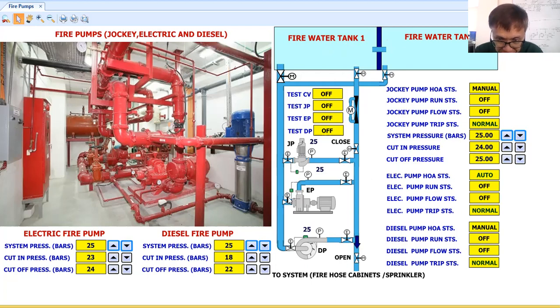So that is how they are checking this electric pump. First zero flow, then 50% flow: they will open this valve at 50%, check the flow, and it will be recorded. Then the third step is to run the pump at 100% flow, meaning this valve is 100% open, and they will measure the flow rate. It will be recorded and checked to see if it passed the requirement. Likewise for the diesel pump, they will do the same thing.